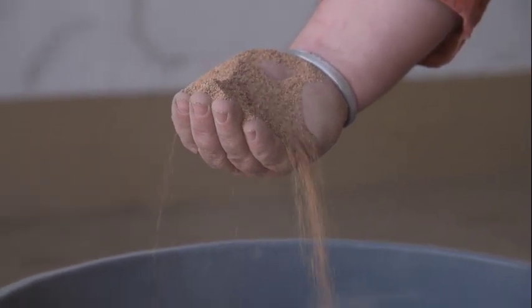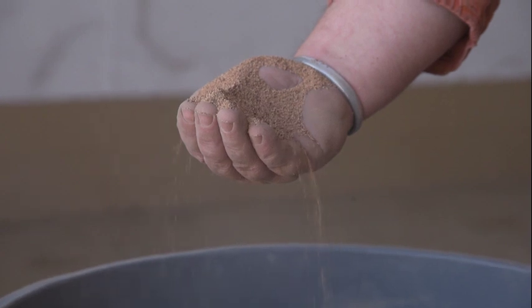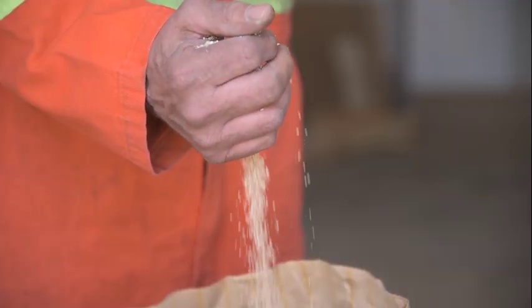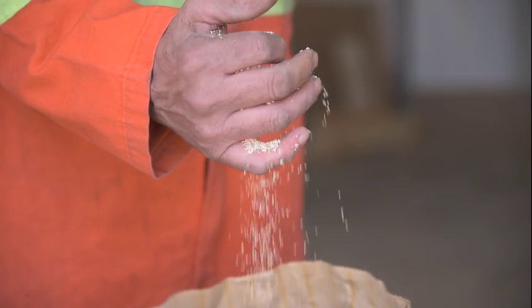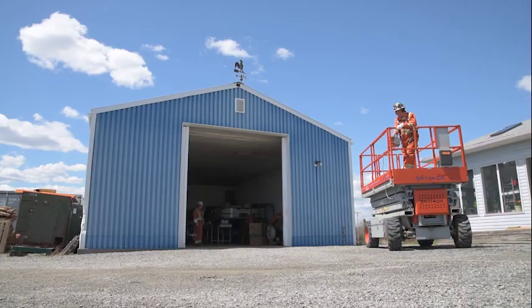Using ground up corn cob as an abrasive cleaner does a great job because it not only removes the debris and carbon and all the other nasty stuff and contaminants, but it also dries up the switchgear, because this product has about a 7% moisture content. So when we're using it to clean switchgear or whatever the case may be, we're removing all the moisture within that piece of equipment, which is fantastic, because that's what that switchgear needs.